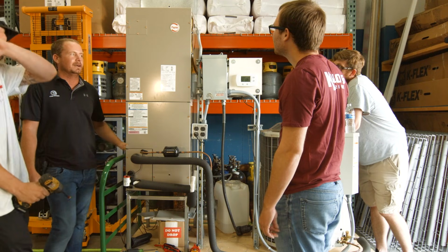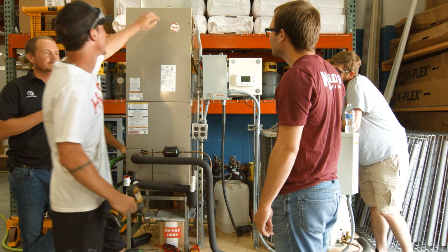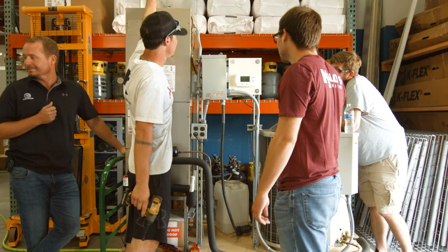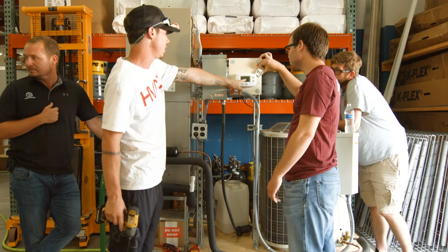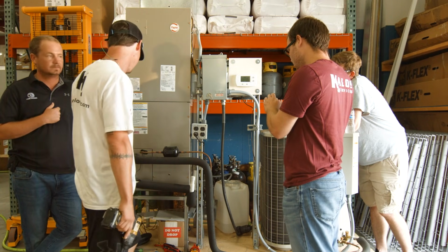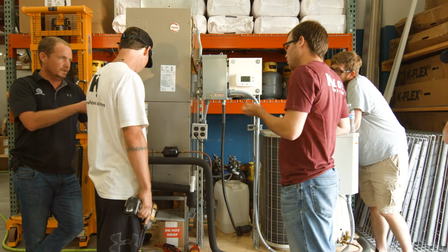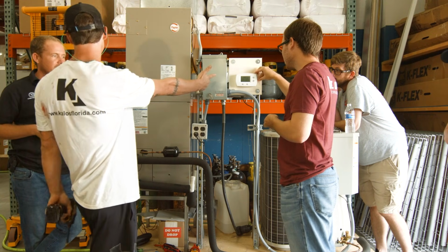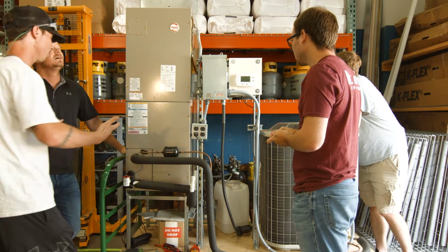All right, so what do we got going on? We don't have blower going, system's not in delay. Does have batteries in it. All right, you're always checking. He's checking the float, which is good practice, starting with batteries out and system shut off.